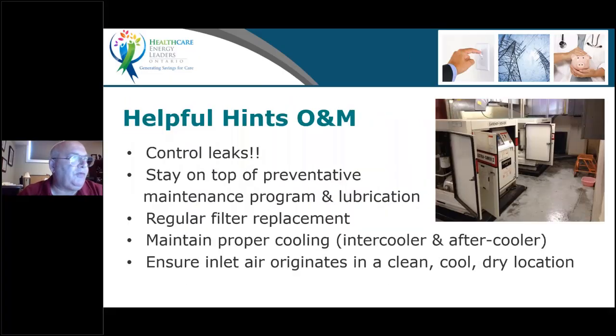So helpful hints when it comes to systems is control the leaks, stay on top of the PMs. You don't want compressors failing because someone's forgotten to change the oil or top up with oil. Regular filter replacements, maintain proper cooling of the intercoolers and aftercoolers, and ensure that the air originates from a clean, dry, cool location. Too many times I've seen compressors stuck in the corner of a boiler room, and they continuously fail because of the high atmospheric temperatures. They virtually cook the oil inside the screws, and they also affect any type of drying systems, whether it's desiccant or refrigerated. Sitting inside a boiler room that's not properly ventilated, you continuously run into issues.